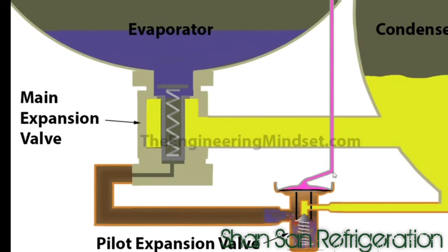used. So as that pressure increases and starts to push down on that diaphragm, it pushes against the piston rods, and these rods push the valve head down, and that causes a slight gap to form there, and this allows refrigerant to start flowing out. So the refrigerant is starting to flow from the condenser through here and into the pilot valve, and then that is going to start to flow through into the liquid line.